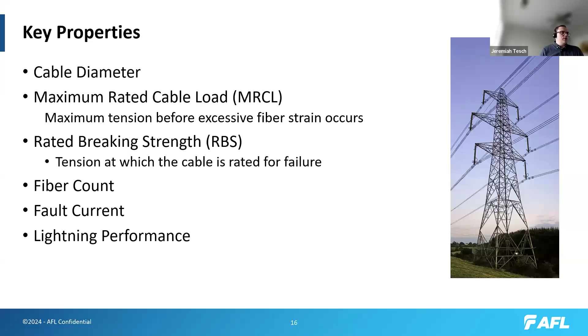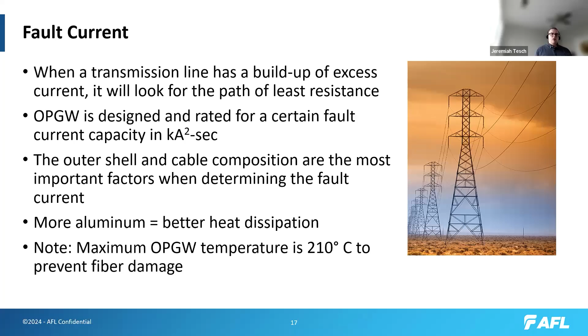And then the fault current is, like I mentioned, when you have an excess buildup of current. This goes for the path of least resistance. So OPGW is designed and rated for a certain fault current capability in kiloamps squared seconds. And this is generally related to how much conductive metal is in the cable. So you've got your aluminum pipe, your aluminum wires, those definitely contribute to that rating. And then, like I said, more aluminum, better heat dissipation. OPGW is typically designed to IEEE 1138, the OPGW standard, and I believe it's tested in the lab up to 180 degrees C typically, but different manufacturers may vary their actual rating beyond that a little bit. We typically go up to 210 Celsius in our cables, but it just depends.